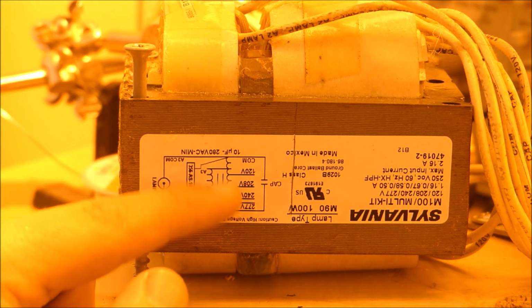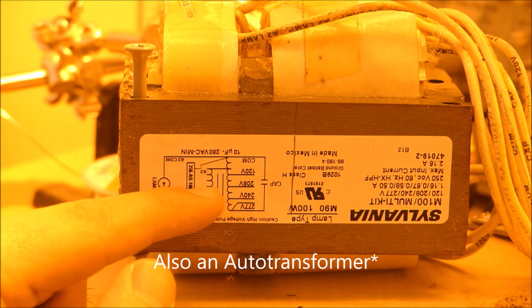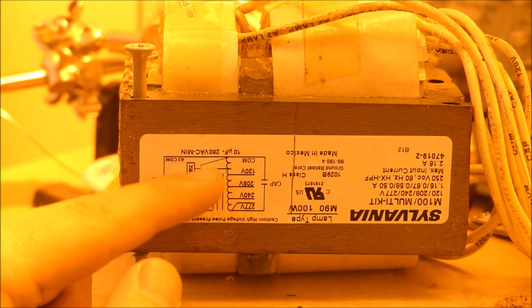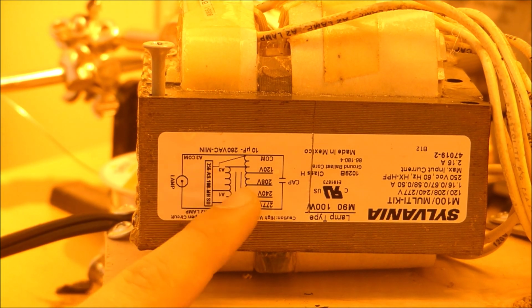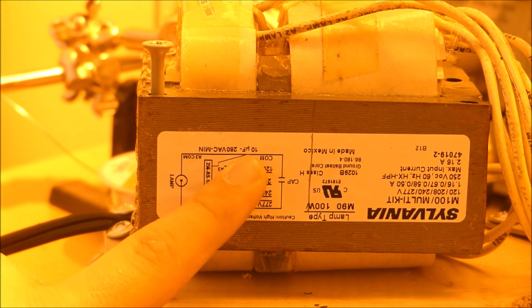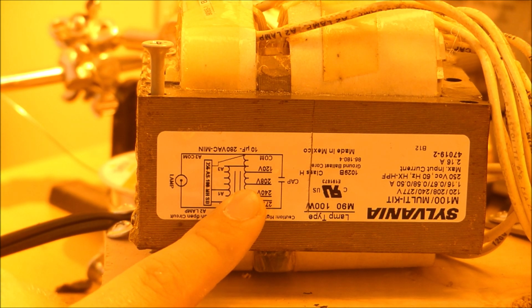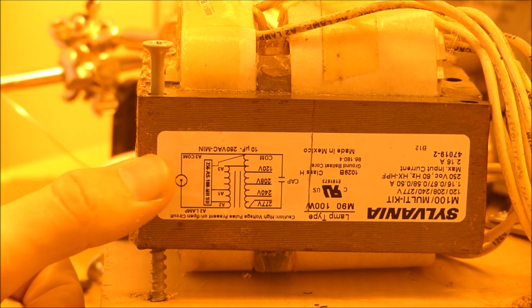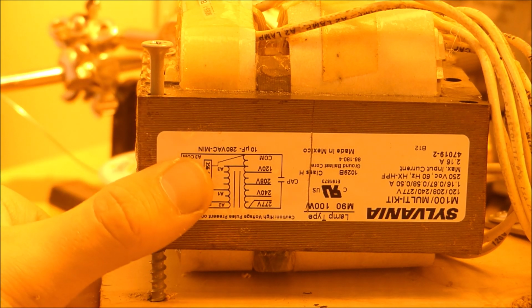Now the reason that there's this big thing right here, this big transformer, is to act as a ballast. Now the reason you need a ballast, this transformer, is because sodium vapor lights operate in something called the negative resistance region. That means that they have negative resistance. As the voltage rises, the current falls, and as the voltage falls, the current rises. It's opposite of normal resistors. That means that this thing needs to have a ballast on it to keep it from going into infinite current.